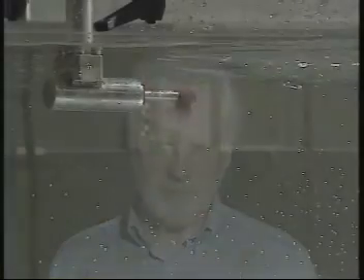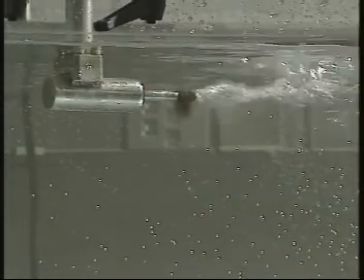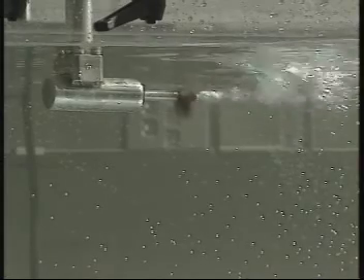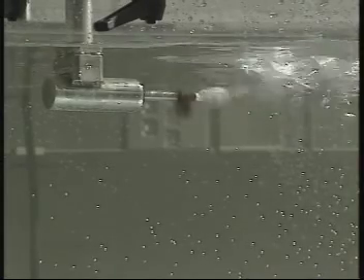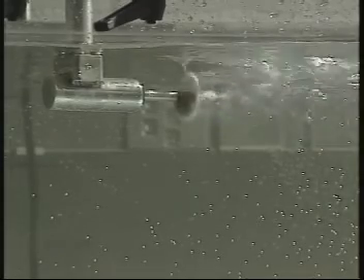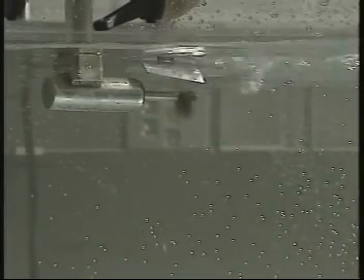If the propeller is too close to the surface when running, a vortex can form. This will draw air and swirling flow into the propeller, causing vibrations and thereby drastically shortening the life of the mixer seals and bearings. Flygt can always give you the minimum recommended submergence. The use of a Flygt vortex suppressor will allow the tank to be pumped down further while the tank is being emptied.